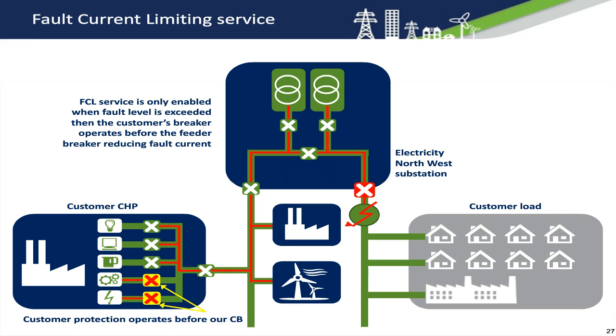If we can reduce the fault current to a lower, safe level before the circuit breaker operates, we won't need to upgrade any of the network equipment, which can be very expensive, or the customer may not have to pay an expensive connection charge. One way of reducing the current is to disconnect the customer's motor or generator. This could happen instantly using new technology deployed as part of Respond. Once the fault section has been isolated, the motor and generator can be switched back on. The rest of the customer's equipment would remain on as normal during this fault, as only the selected items of plant would be interrupted, and only until we have disconnected the fault, which could take up to 10 minutes.